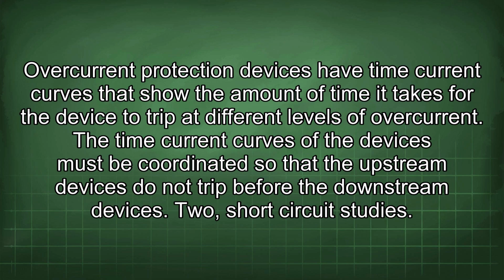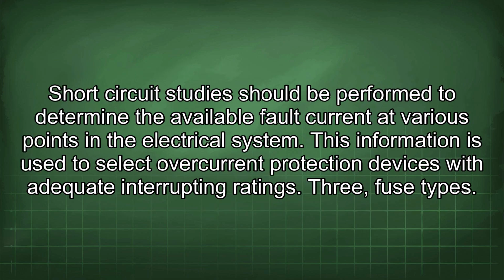The time current curves of the devices must be coordinated so that the upstream devices do not trip before the downstream devices. 2. Short circuit studies. Short circuit studies should be performed to determine the available fault current at various points in the electrical system. This information is used to select overcurrent protection devices with adequate interrupting ratings.